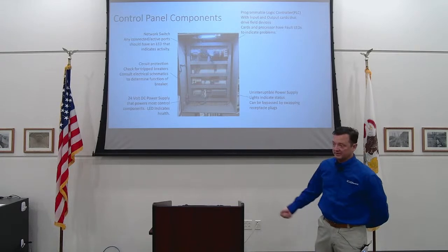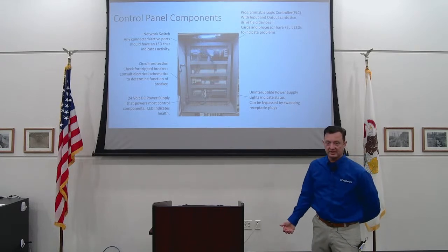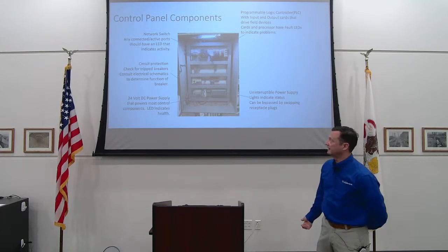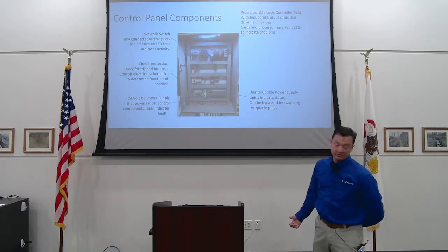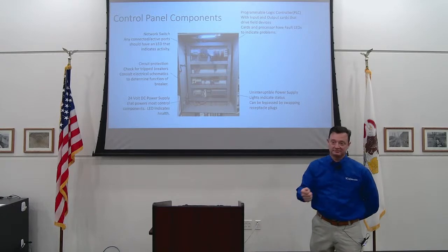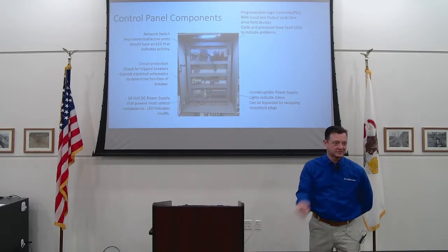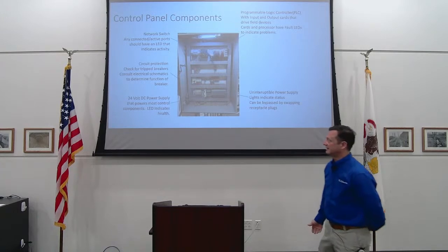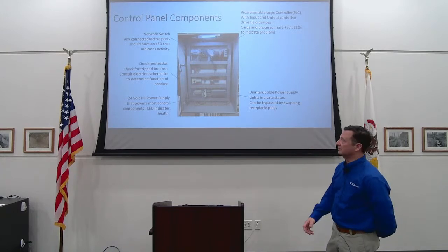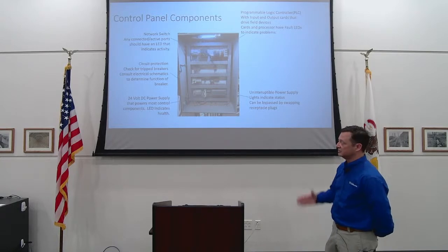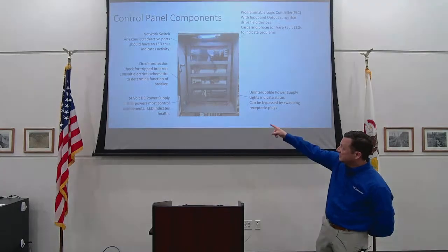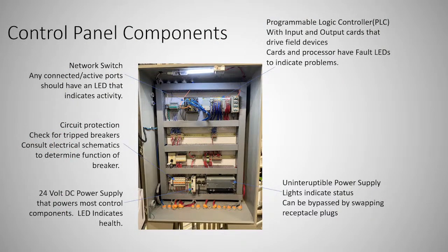Circuit protection, circuit breakers, be able to diagnose if a circuit breaker's tripped out. Obviously, that's a really quick find inside a control cabinet. But normally, if something's tripped, it's almost never a bad breaker. Something else has caused that thing to trip. So I hate to just flip things back on and walk away, but that at least sends you down the right path. And then this device down in the middle of the cabinet is the 24-volt power supply. That's what powers up all the automation components, and that's a really typical item to fail in a PLC cabinet.